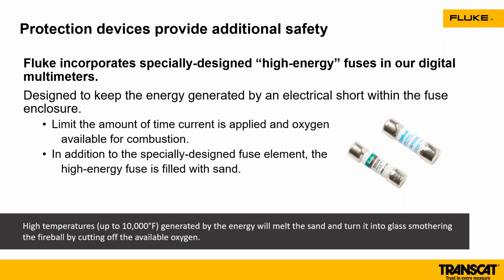How many times have you gone out, and we're not talking meters in this case, we're talking about just applications. I've literally gone out and somebody put a nail or something where a fuse should be in a split phase panel. Inappropriate, unsafe, could potentially cause a serious fault because they didn't take the time to put the right fuse in or do the job correctly.